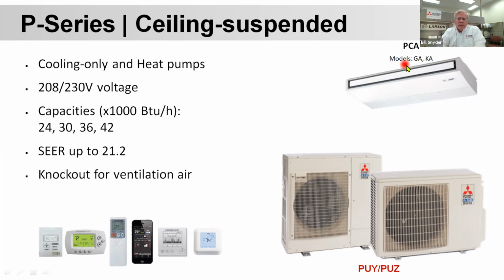This particular unit is a ceiling suspended. It hangs from the ceiling or mounts tight to the ceiling. All of your connections are made in this back corner. And this does have ventilation air available. You can suck some outside air in for a commercial site. And these are available 24 through 42,000 BTUs, and they throw air over long distances. And in the submittal data or on this little book here that is called the Pocket Reference Guide, it lists the airflow for all of this equipment we've talked about. And this particular unit has the furthest airflow. So this would work very well in a large room.